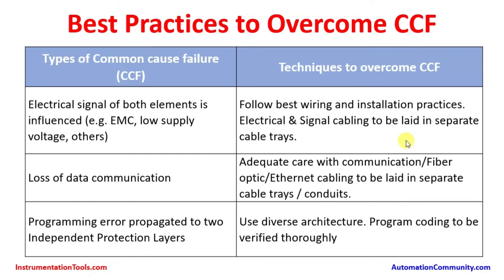Motors or turbines operate at very high voltages like 3.3 kV, 6 kV, or 11 kV, while instrumentation transmitters in the safety instrument system and basic process control system operate at only 24 volts. These two cable types must be laid in separate cable trays with enough distance between them; otherwise, electromagnetic interference can impact the measurement.